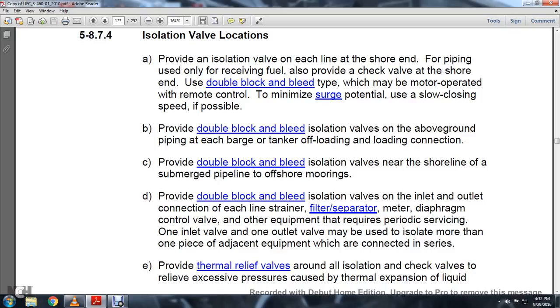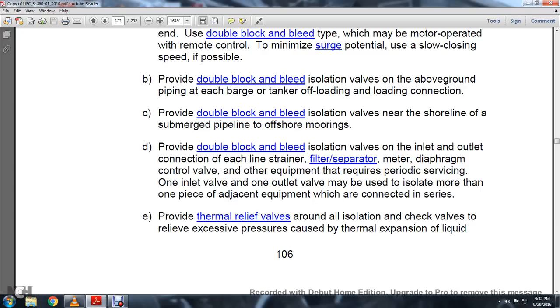B. Provide a double block and bleed isolation valve above the ground at each barge and tanker unloading and loading connection. Provide double block and bleed isolation near the shoreline of the submerged pipeline with offshore moorings. Provide a double block and bleed isolation valve with an inlet and outlet connection for each line strainer, filter separator, meter, diaphragm and control valve, and other equipment that requires periodic servicing.